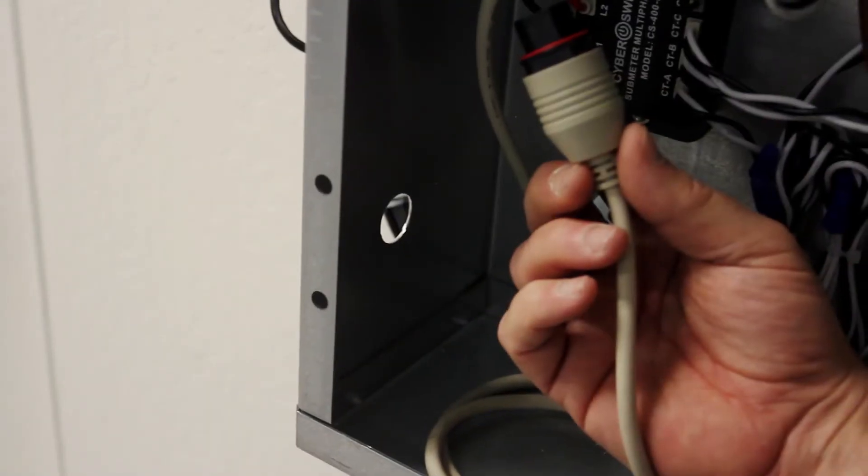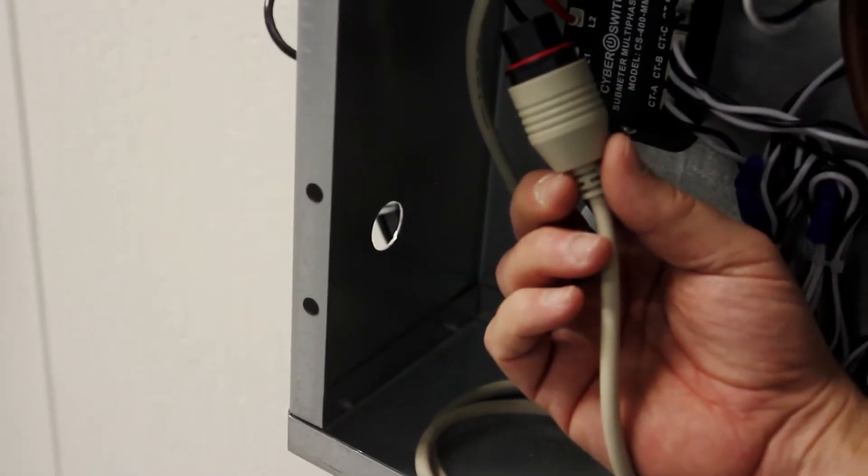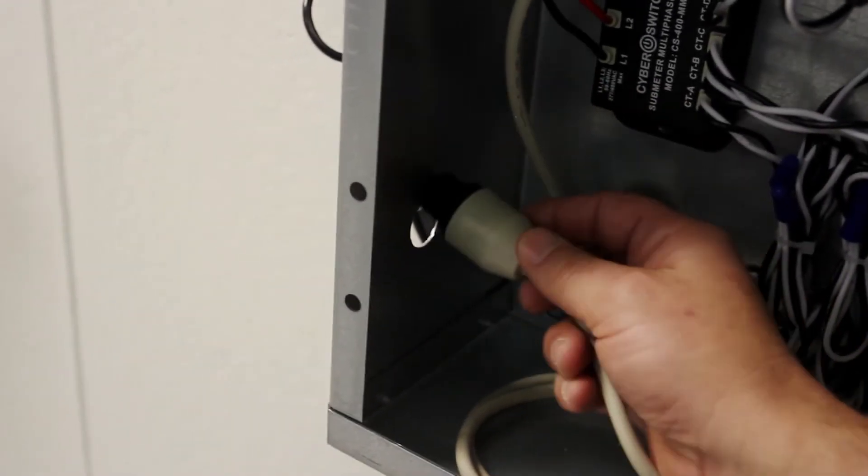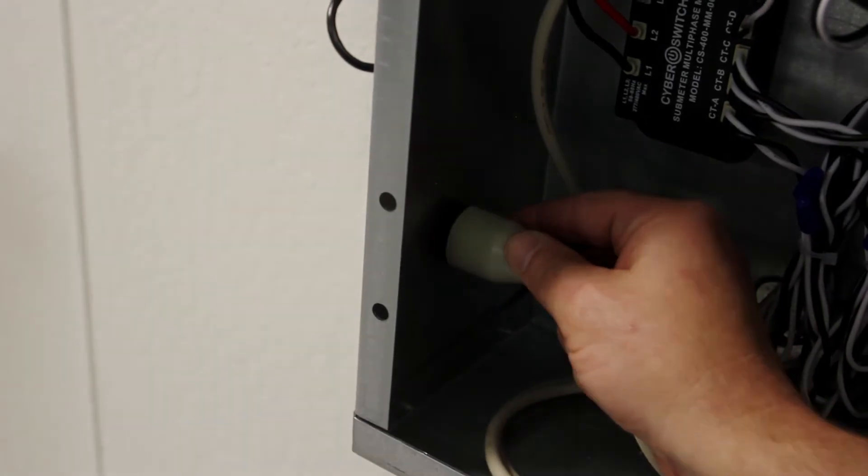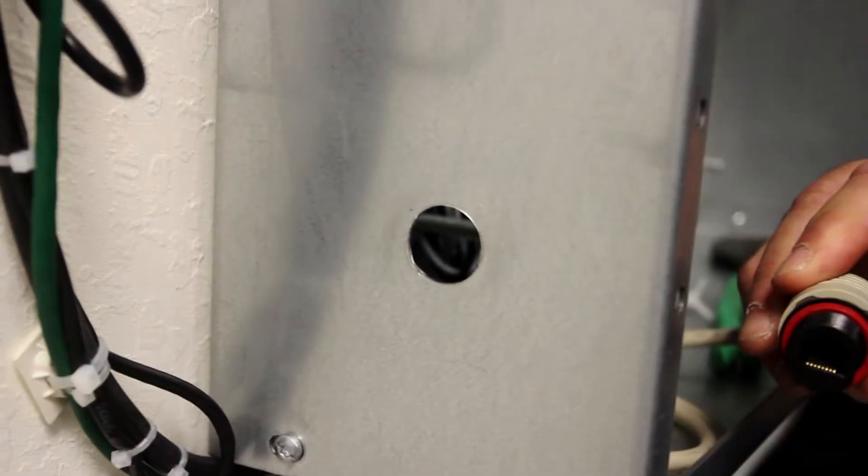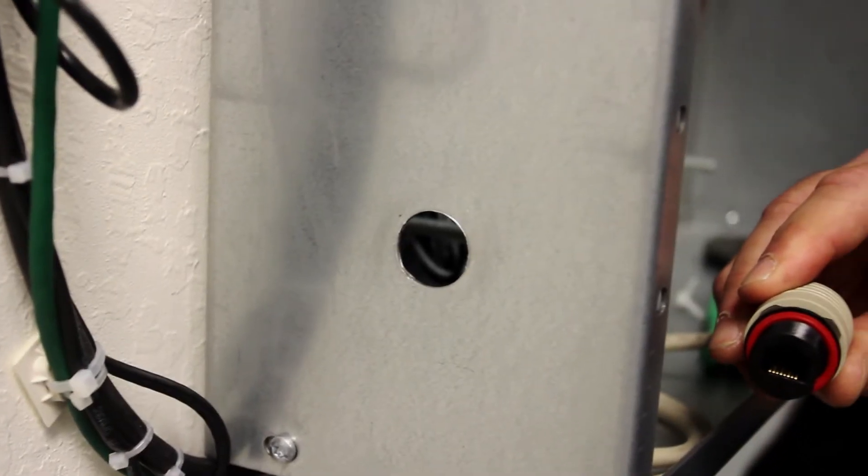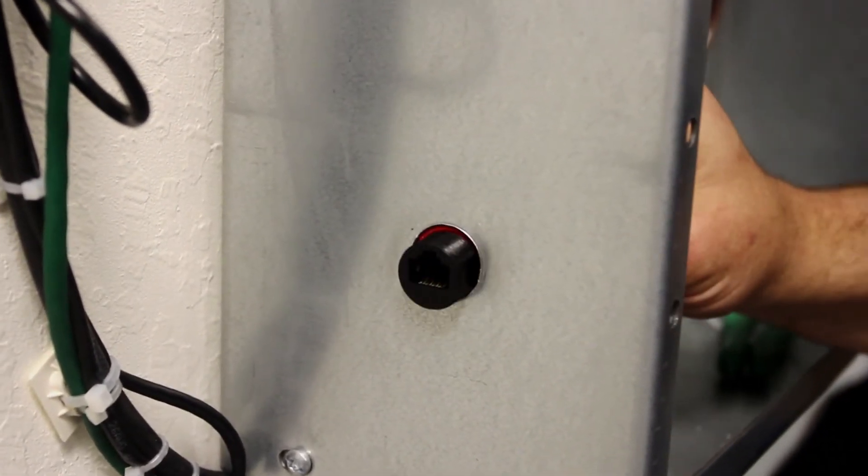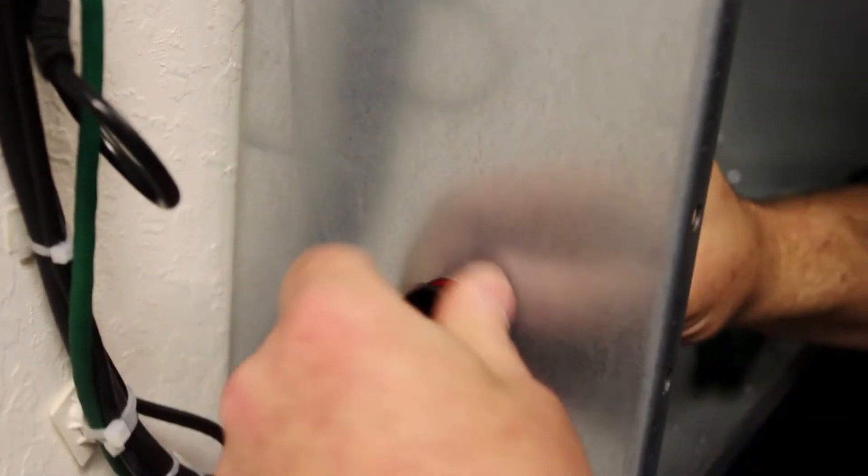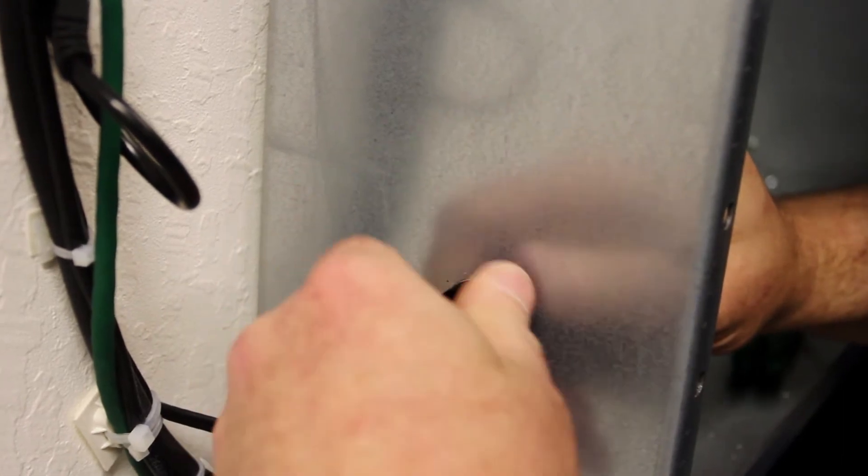Drill a 7/8 inch clearance hole to secure the panel mount connector from the module. The connector is secured using the plastic nut supplied with the kit. You will need to connect the module to a submeter hub at this port using a standard RJ45 ethernet cable.